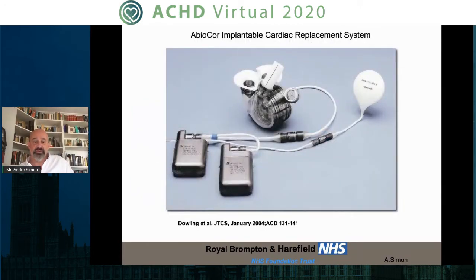Then the AbioCor was there. That was a fully implantable system, driven here with these batteries. One of the main problems of this system is that it is a displacement device. It actually pumps. It has an expanding and contracting chamber, and it needs some sort of expansion chamber. And this here is the expansion chamber, which used to go into the axilla region of the patient, and that would break after a maximum of about half a year. Other than that, it didn't function.